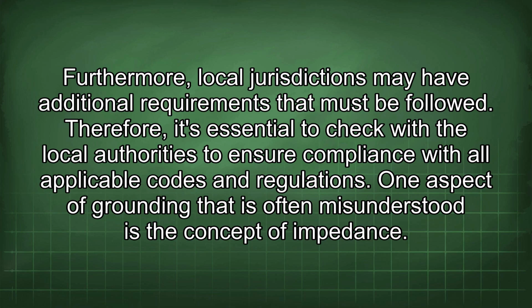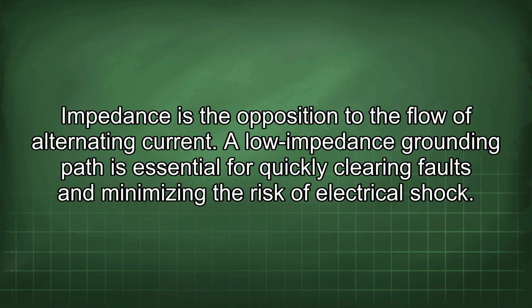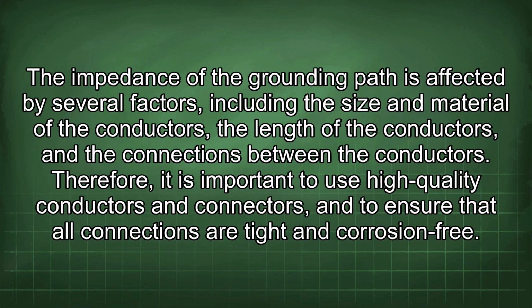One aspect of grounding that is often misunderstood is the concept of impedance. Impedance is the opposition to the flow of alternating current. A low impedance grounding path is essential for quickly clearing faults and minimizing the risk of electrical shock. The impedance of the grounding path is affected by several factors, including the size and material of the conductors, the length of the conductors, and the connections between the conductors. Therefore, it is important to use high-quality conductors and connectors, and to ensure that all connections are tight and corrosion-free.